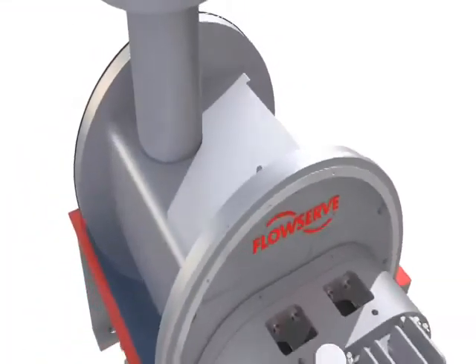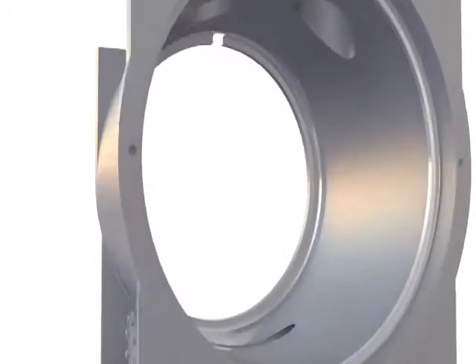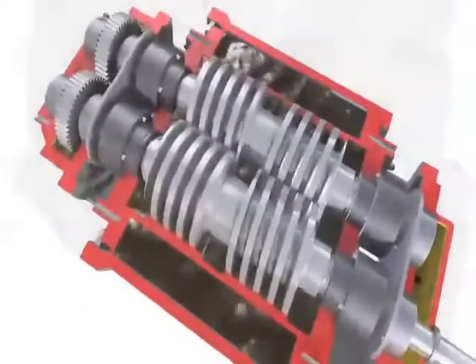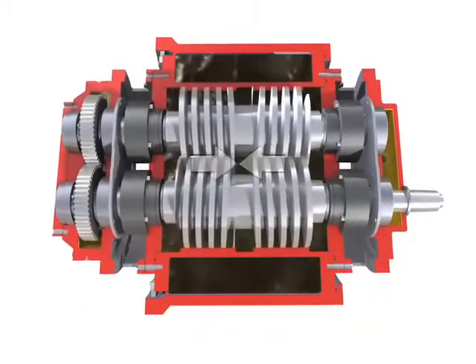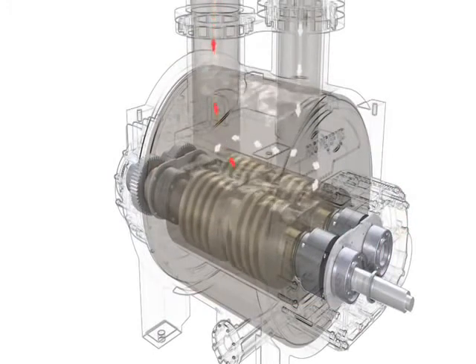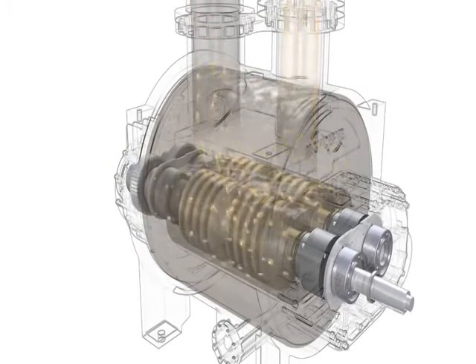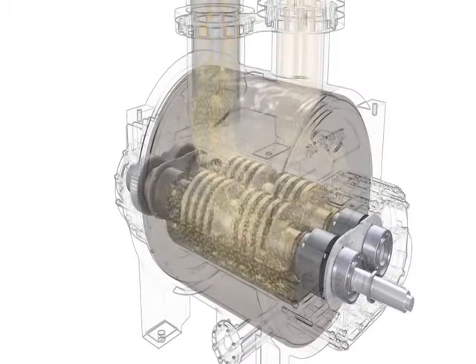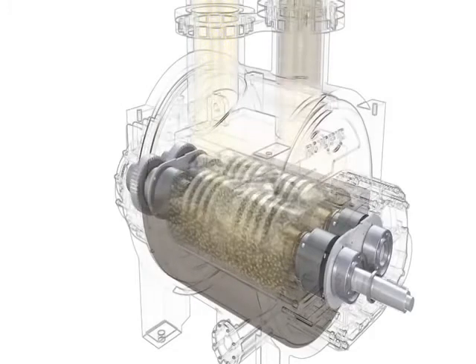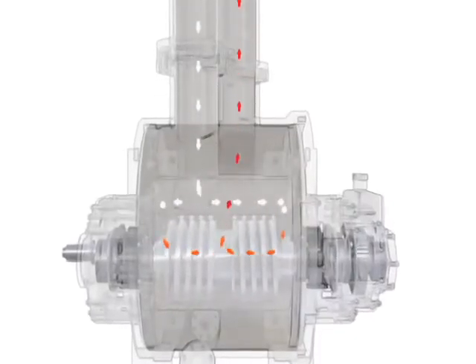All components that comprise the pump casing are produced from castings or are machined from pressure boiler plate. This approach eliminates the potential for weld failures and sulphide stress corrosion cracking during operation. The double suction design ensures the mechanical seals are only exposed to suction pressures for optimized operating conditions. A dynamic liquid seal is required between the intermeshing screws and casing when pumping multi-phase mixtures with high gas volume fractions or during gas slugs. The MP1 incorporates a large chamber between the outer and inner casings which captures liquid that keeps the screws flooded, ensuring a dynamic seal is always maintained and also dissipates the heat of compression associated with multi-phase pumping.